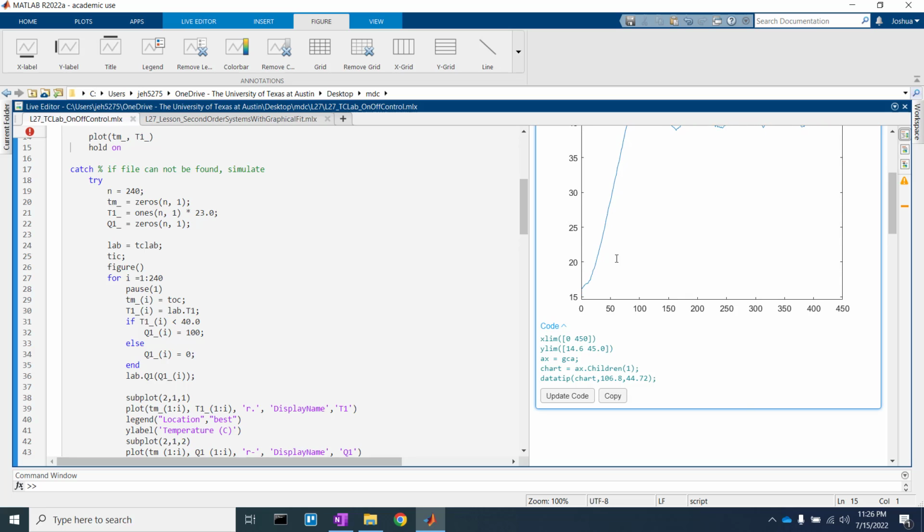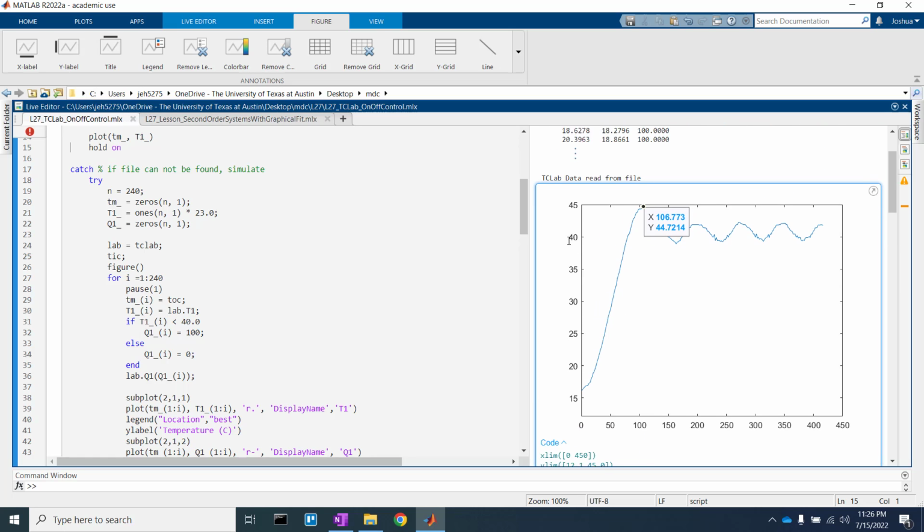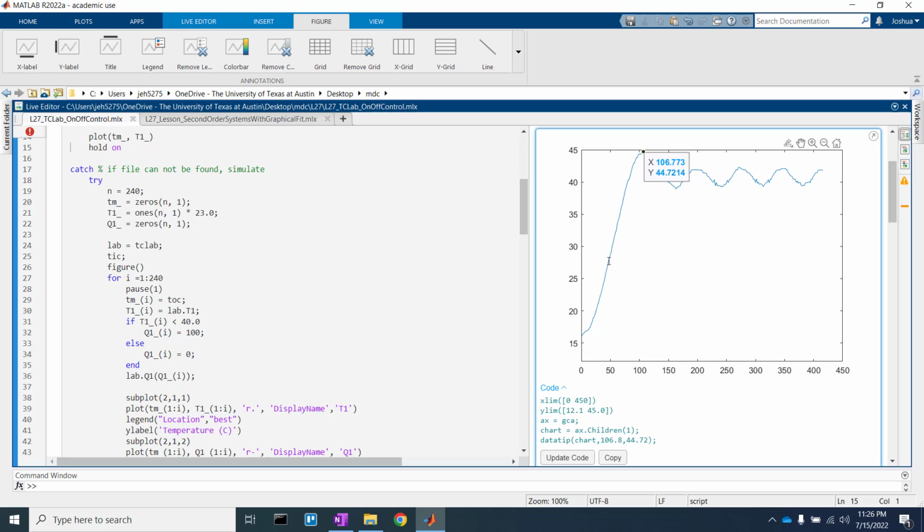We'll do that like we've done before by just looking at, since we started just about instantaneously, where this line would cross the x-axis. Right here at the point of inflection, running down, I'd say that's maybe about right here. So about 5 seconds. There wasn't much dead time in this system. We know from past experience, though, our dead time is more like 10 to 15 seconds. We plot all these points. Go ahead and clear them.